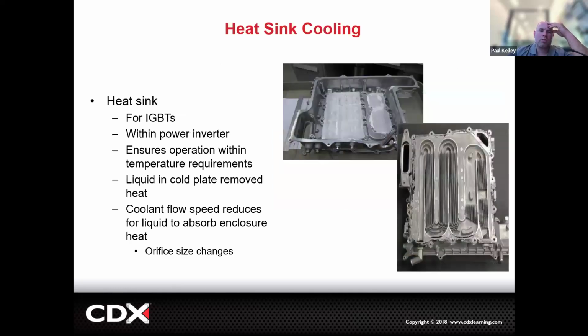There's another type of cooling, which is the heat sink, especially for insulated gate bipolar transistors (IGBTs). These transistors generate a lot of heat, and we have them contact a heat sink using a good heat transfer paste. The IGBT gets hot and transfers its heat through the paste into a larger piece of aluminum - the bigger that piece of aluminum, the bigger the heat sink. We do this with electronics as well, like LEDs. If it's just IGBTs, it may not make a ton of heat.